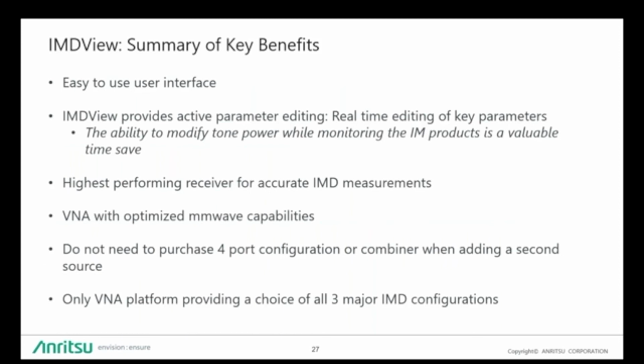And that's just a quick summary of benefits for the IMDView software. The main one is that this is very easy to use. All you have to do is go in there. You can put in the tone deltas. You can set the power levels, center frequency, and it's basically a platform for carrying out accurate IMD measurements.